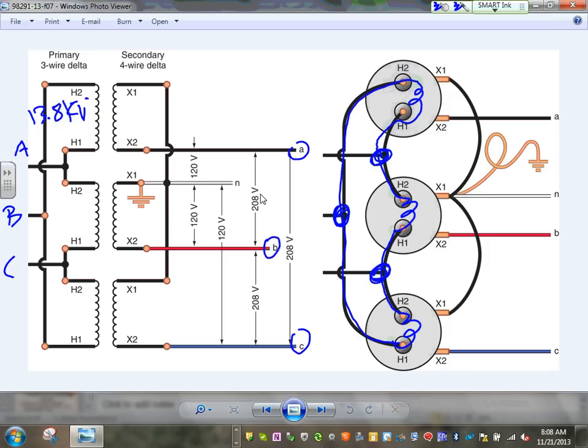Look how easy the Y is. The Y is: bring one side of all the transformers tied together. All the transformers tied together, one side. Can you guys see that side? And that will be your neutral. And the other side of each coil, bring phase A, phase B, phase C. Now how easy is that? So easy, guys, the connection.